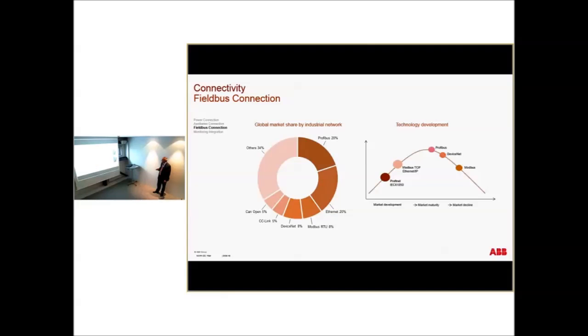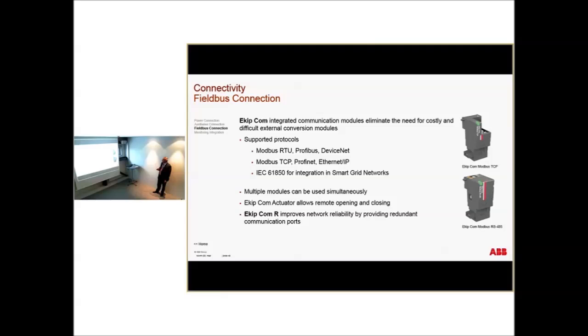Obviously, there are also some others. What we decided to do is to support all protocols: Modbus RTU, Profibus, DeviceNet, Modbus TCP, Profinet, Ethernet IP, and IEC 61850 for medium voltage. This is very important. This is something that we missed. We cannot communicate with medium voltage if you don't have 61850 included. What is important is that we don't have protocol converters that reduce speed or capability or create bottlenecks. Everything is totally independent. And the information given by the breaker is all transmitted through the communication.